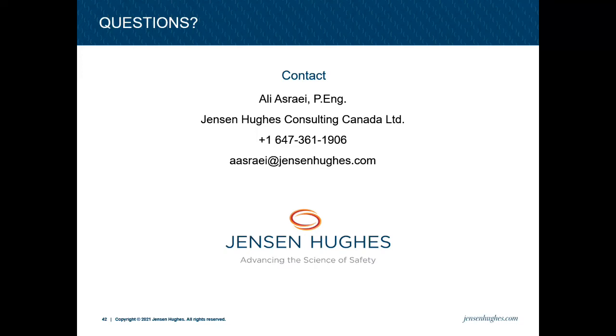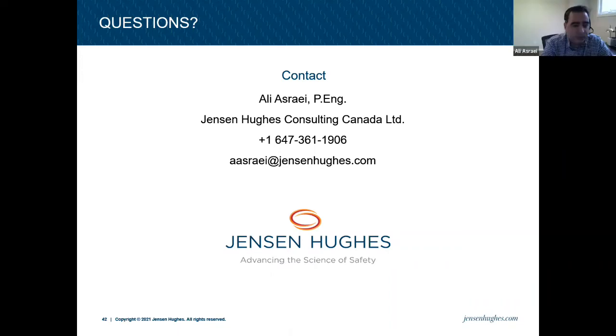And that's where, as Ali was saying, I think it's important to be asking those questions to the person providing the report: how is this acceptable, and justify that. Right, and justify the numbers and the readings that they're getting. Certainly, if you're getting negative pressurization, that's a problem. But once you're in the territory of getting positive pressurization, what is acceptable can vary from building to building.